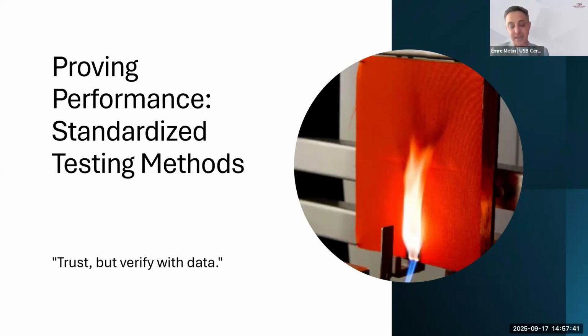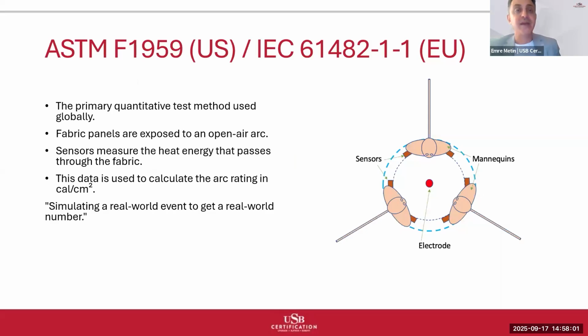When manufacturers claim their garment provides specific levels of arc protection, those claims must be backed by testing according to the recognized international standards. This isn't marketing, it's physics and material science validated through controlled experimentation. ASTM F1959 in the US and also IEC standards.